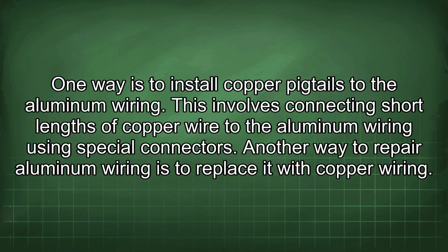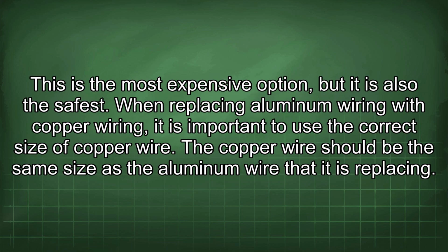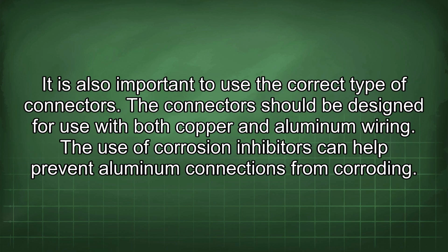Another way to repair aluminum wiring is to replace it with copper wiring. This is the most expensive option, but it is also the safest. When replacing aluminum wiring with copper wiring, it is important to use the correct size of copper wire. The copper wire should be the same size as the aluminum wire that it is replacing. It is also important to use the correct type of connectors. The connectors should be designed for use with both copper and aluminum wiring.